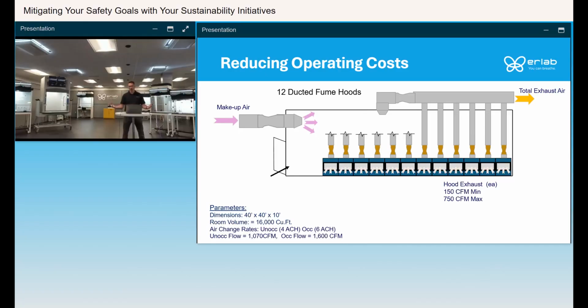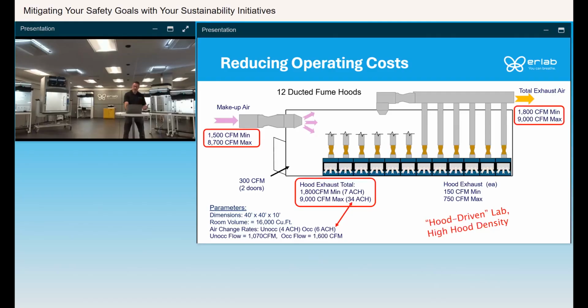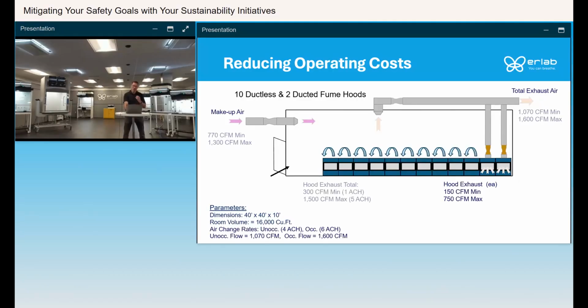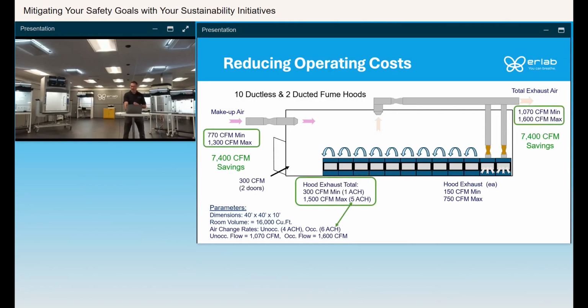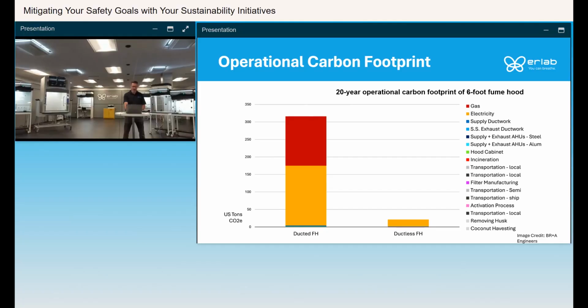So in this example, all 12 hoods, we do see this with chemistry teaching labs, all being ducted. You're going to need about 9,000 CFM of air. So in that same size space, it'd be about 34 air changes per hour, about 28 air changes more per hour than you actually need. Now in this example, let's go with 10 ductless and 2 ducted. So those 2 ducted will keep them below that minimum air change rate, but also provide a hood for dispensing and hoods for satellite waste accumulation. So when you do that, you wind up seeing a significant savings of about $24,000 per year. That's with 35% usage. So with those hoods just being open 35% of the time, or being used 35% of the time with the sashes open, pulling 750 CFM each.